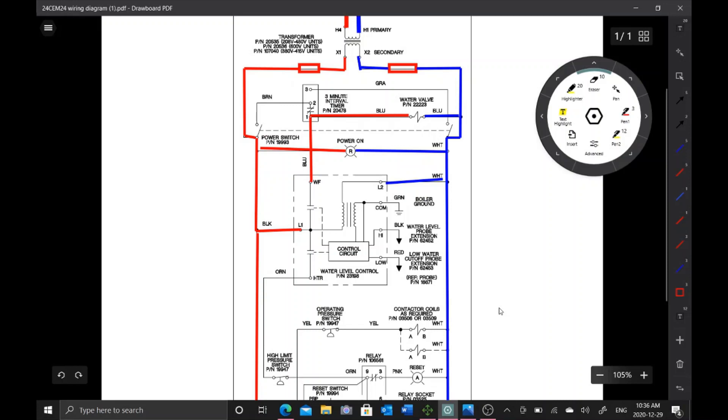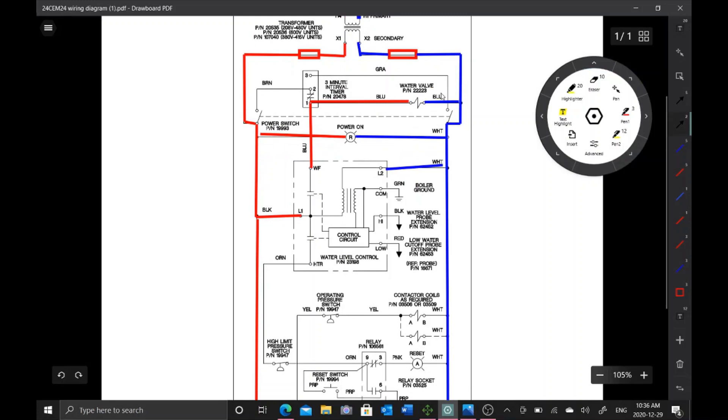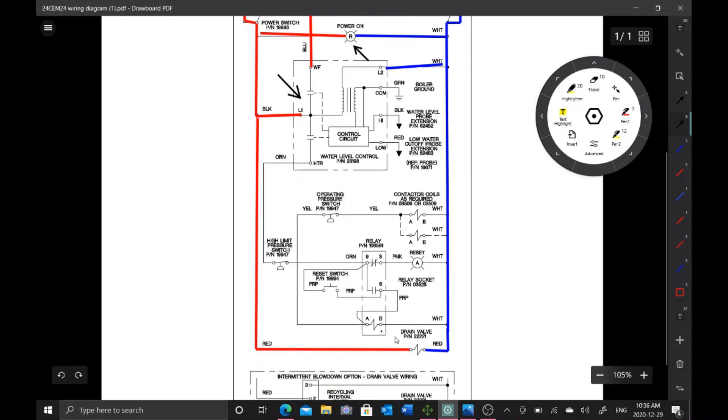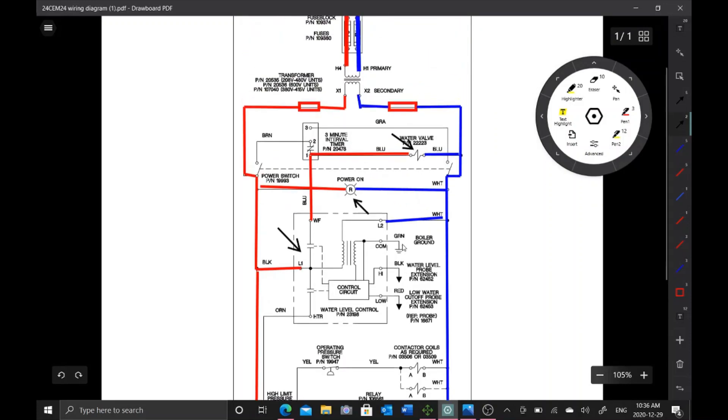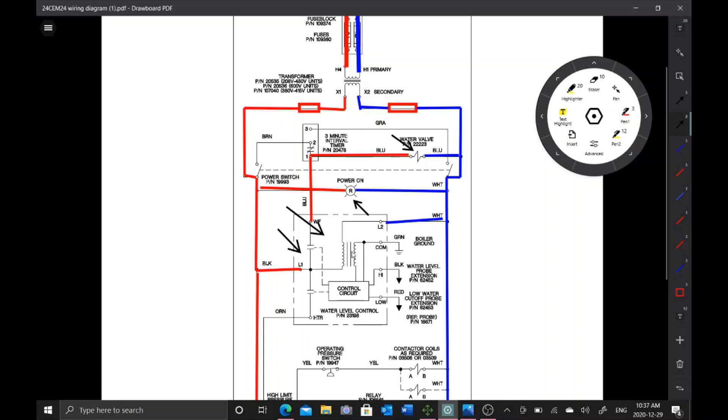The next thing I did was isolate all four of those components that I feel like could be the issue. Sorry you can't see it in the video, I was videotaping someone else. What I did was remove the four loads: I disconnected the wiring here, disconnected the wiring to this board, disconnected the wiring to this light, and disconnected the wire to this drain valve. Now as soon as I disconnect the wiring to this board here, this water valve's kind of out of the circuit, so these two have to be connected together. I disconnected all four of those. That fuse is no longer blowing. What I did next was I started reconnecting things one at a time.